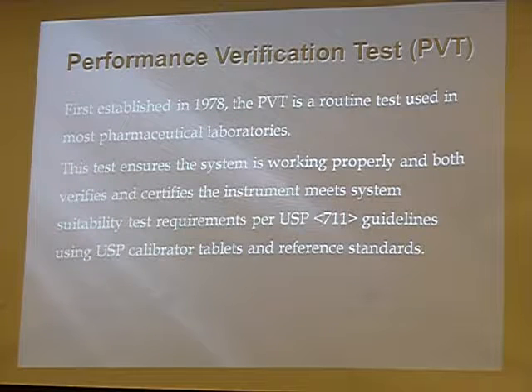But here we have an actual document for the PQ, the PVT. This test ensures the system is working properly and both verifies and certifies the instrument meets system suitability test requirements per USP 711 guidelines using the USP calibrator tablets and the reference standard. So we actually make the chemical drops. We actually drop tablets, prednisone, pull a 30-minute sample at each position, test it with a UV against a reference standard to make sure that it passes within a certain specification as outlined by USP 711.